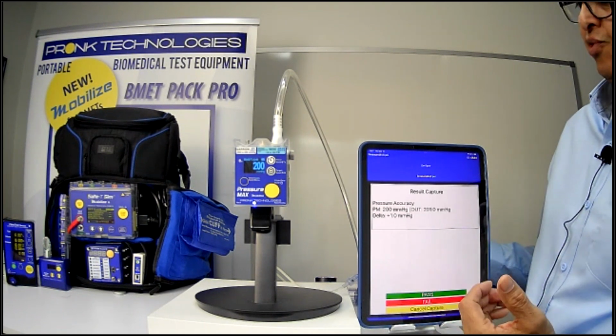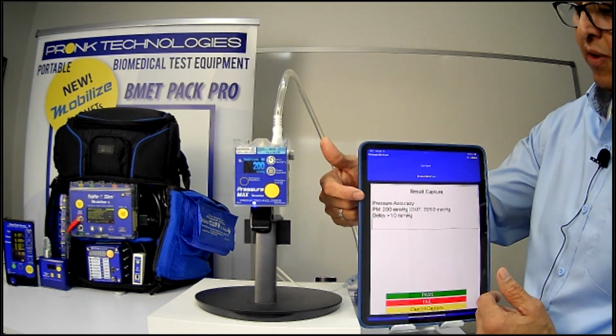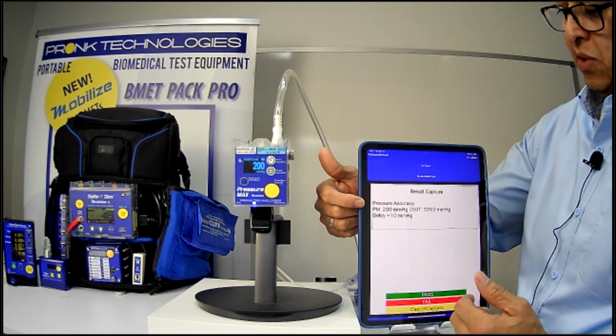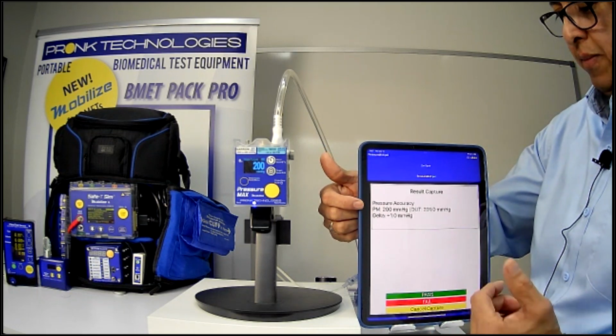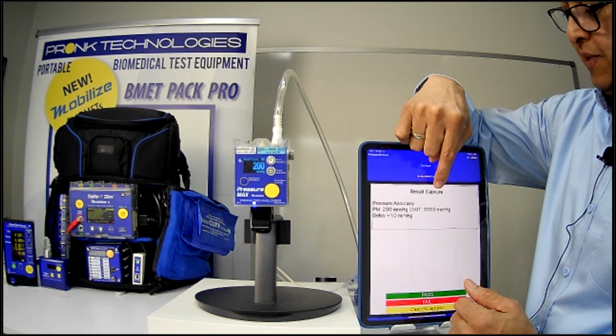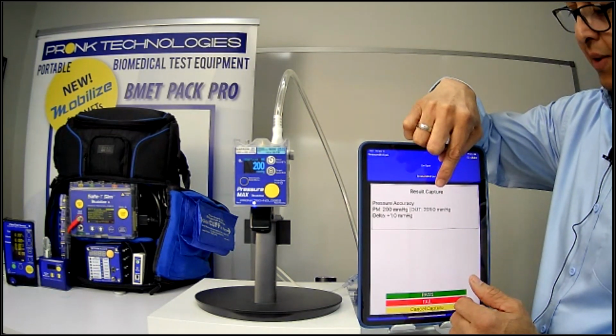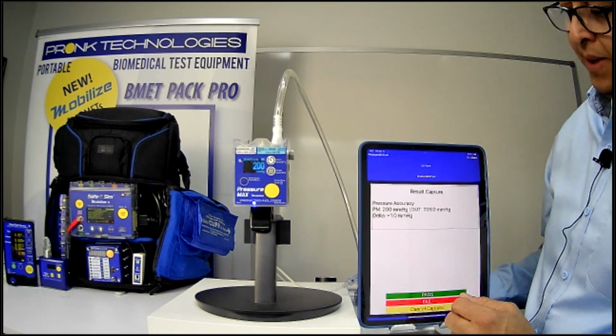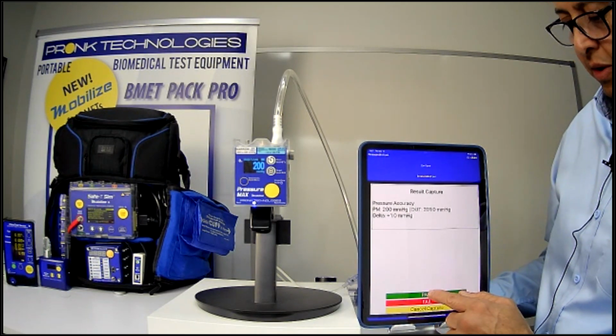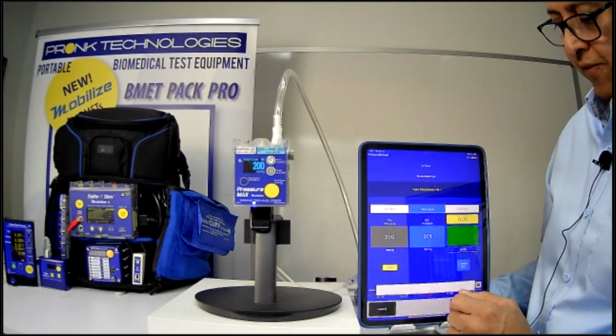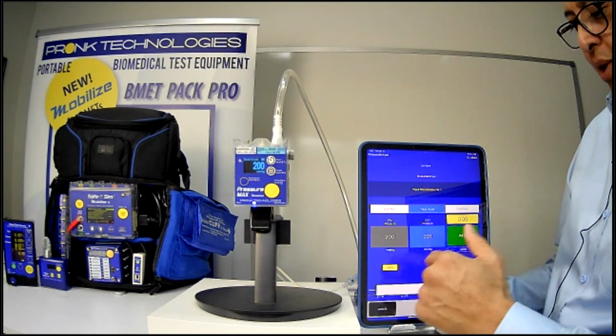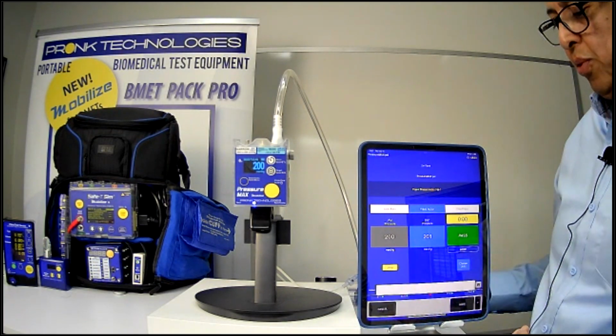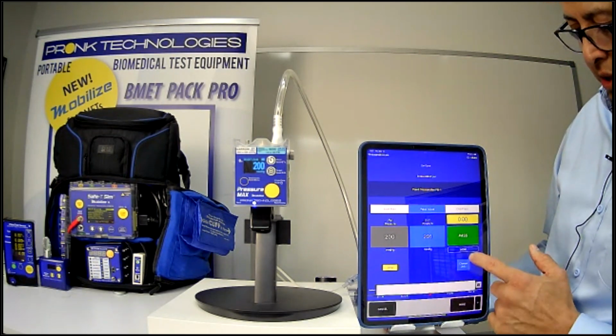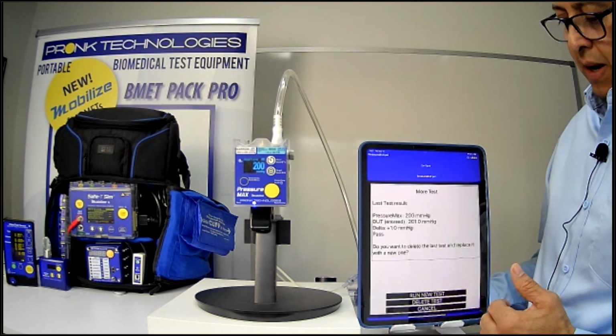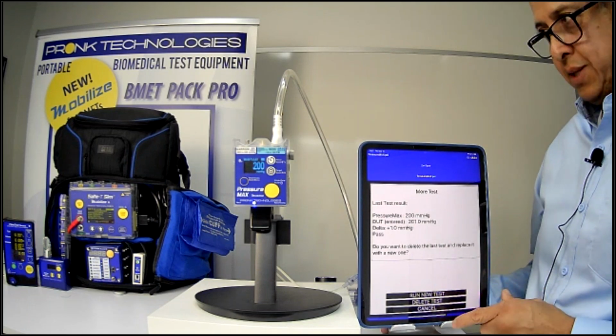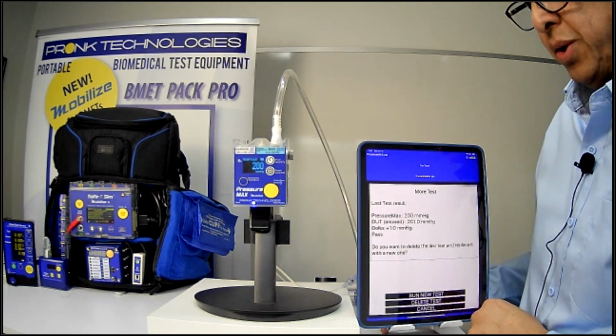So when you do go to the capture screen, you'll be able to see the pressure accuracy for the PM Pressure Max, what its pressure point was at 200 millimeters of mercury. You have the device under test, which is that value we entered in. It measured at 201. The delta between those 2 points was plus or minus 1 millimeter. And depending on your device, pass or fail it and go on. So you're able to do a pressure test here. If you have a device that has multiple pressure calibration test points, you can simply do more. It will give you the option, do you want to replace the result you had last time?